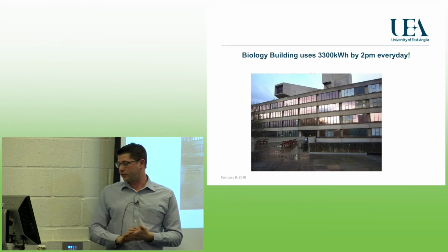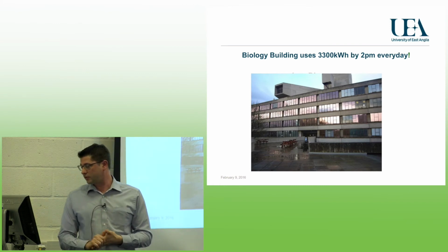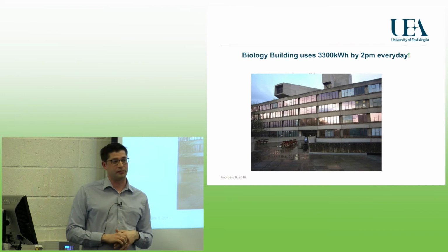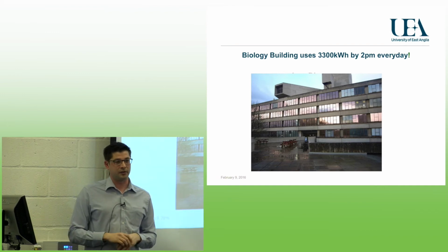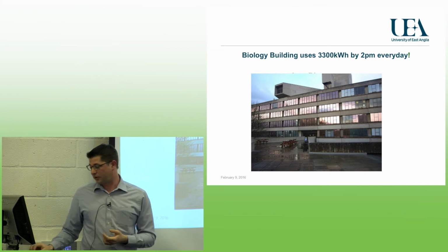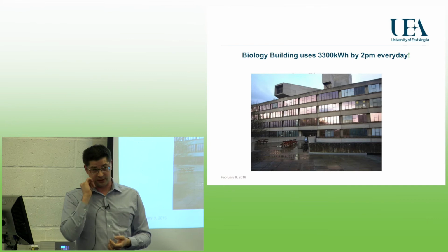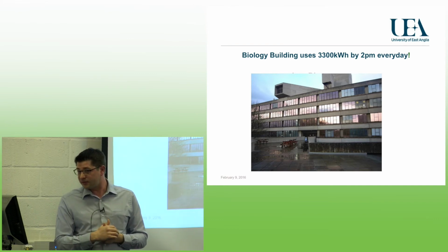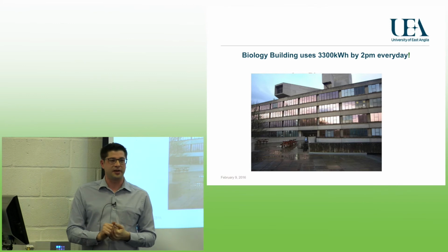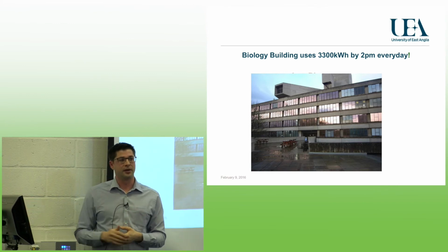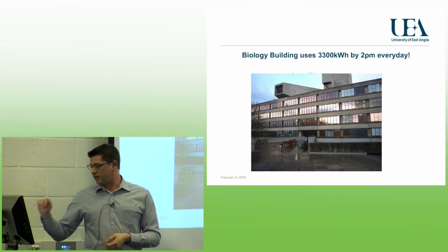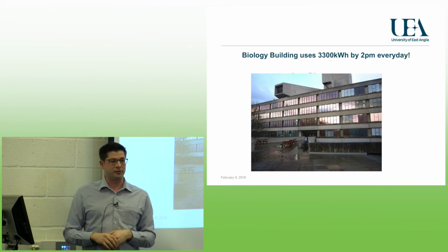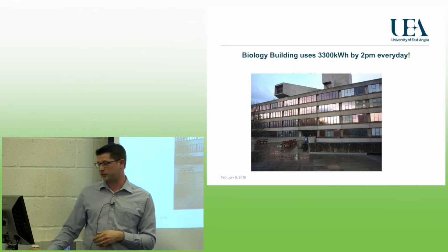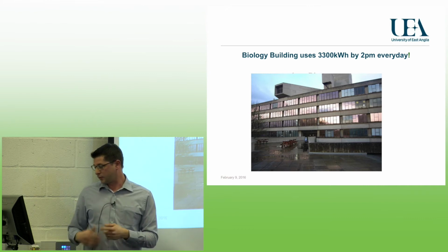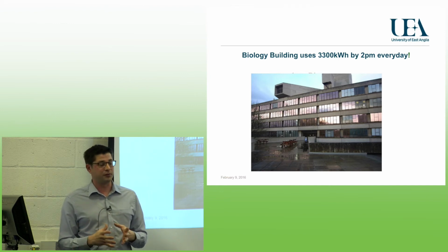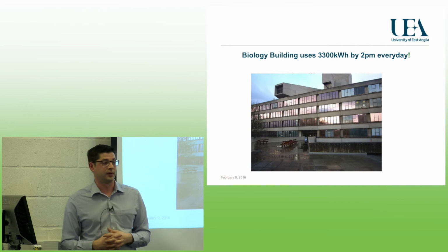Here's an example of how much electricity we use. The typical UK house uses 3,300 kilowatt hours per year; Biology uses that by 2 o'clock every day. Catherine also recently discovered there are 27 minus-80 freezers in Biology and a few in BMRC. Those 27 freezers use the same electricity as 36 houses per year just to keep things cold. Surveys also found the difference between the worst and best freezers is about 4 times, simply due to their age.